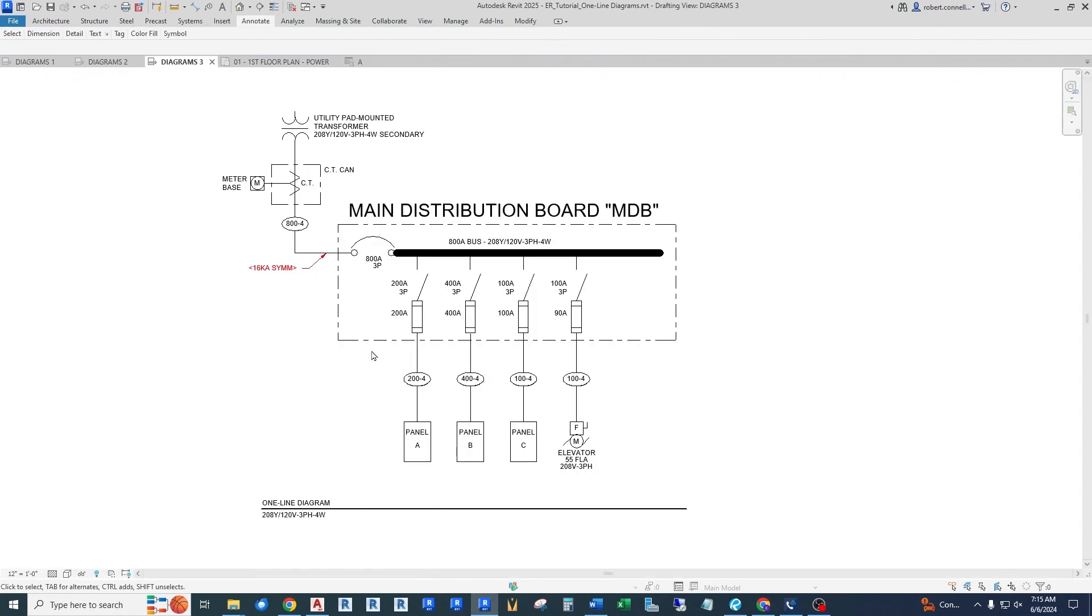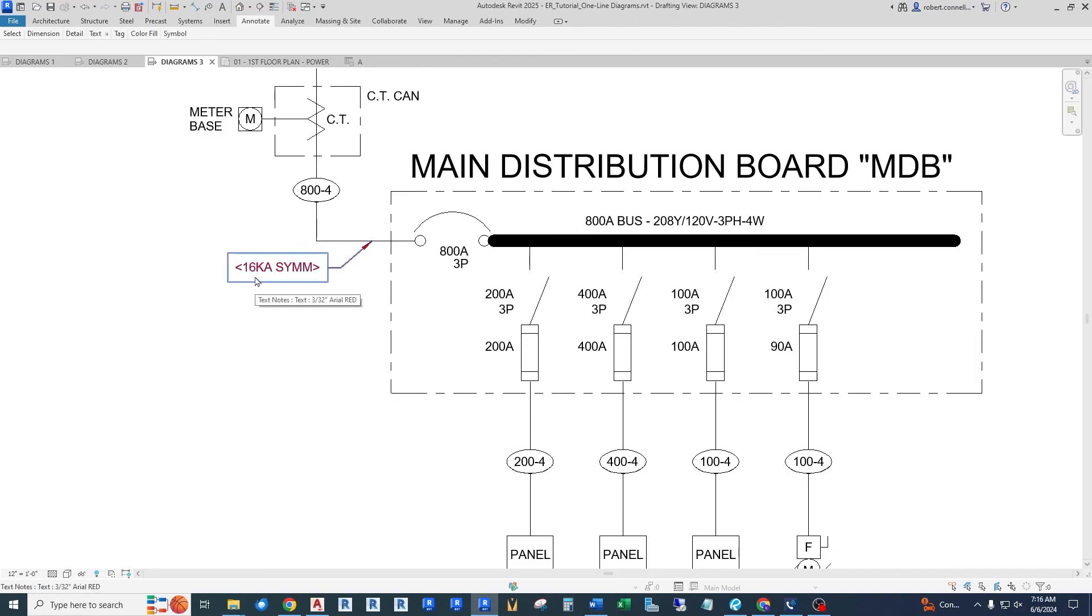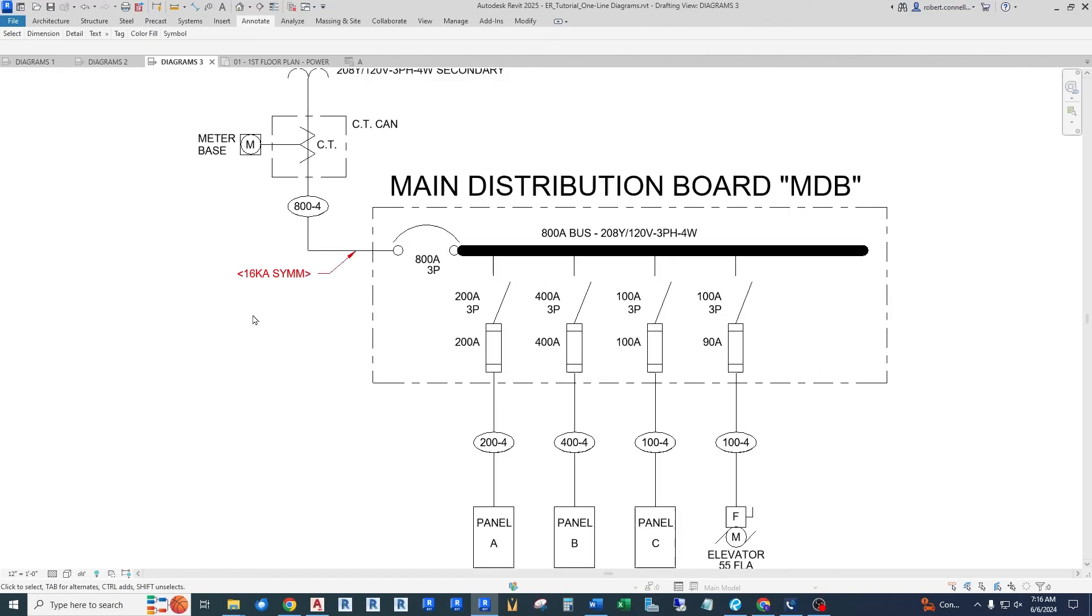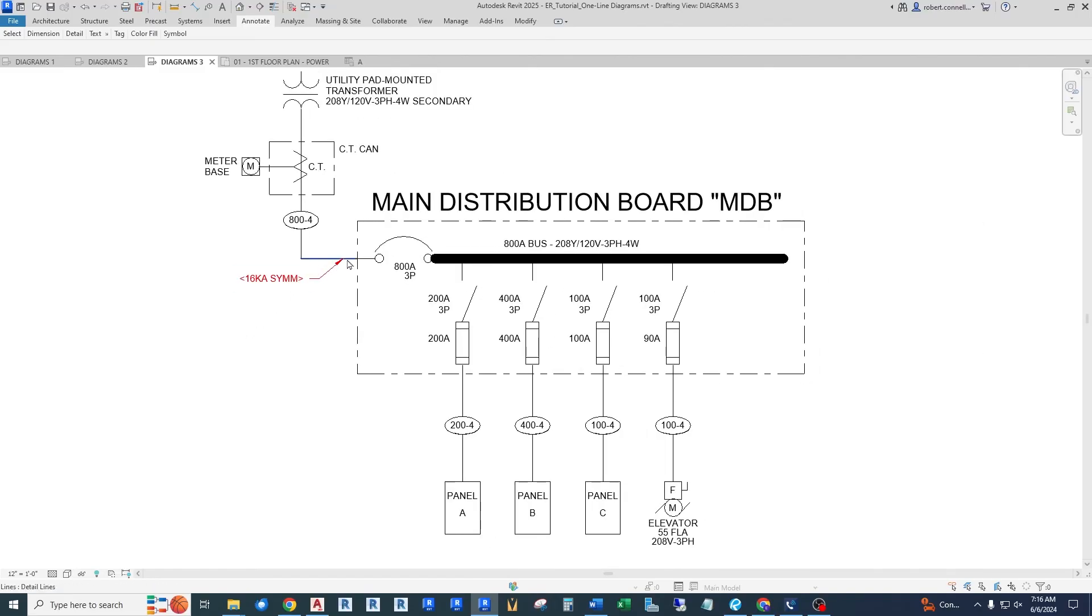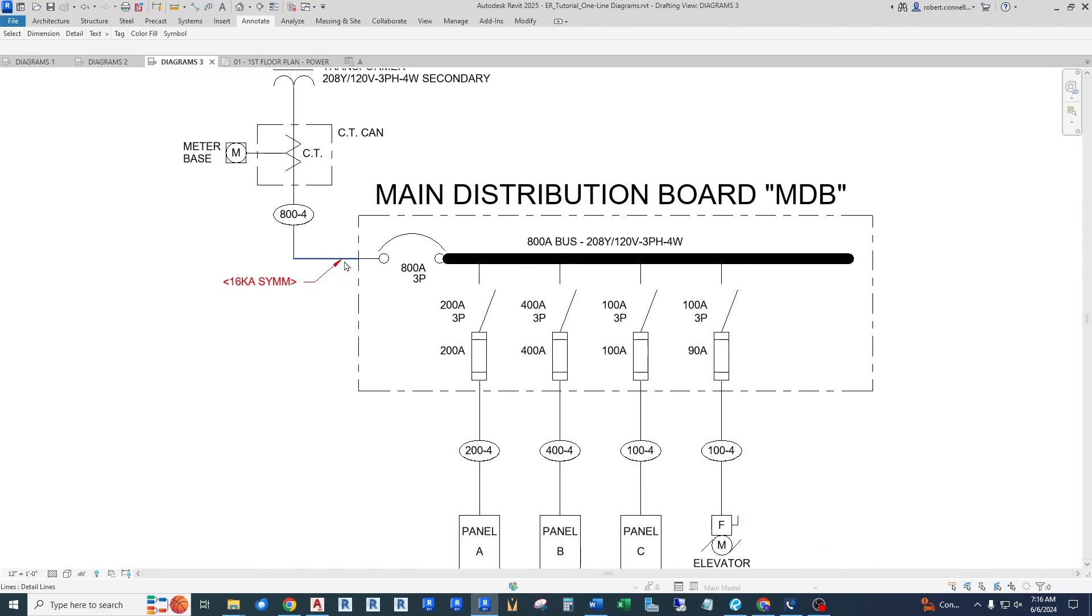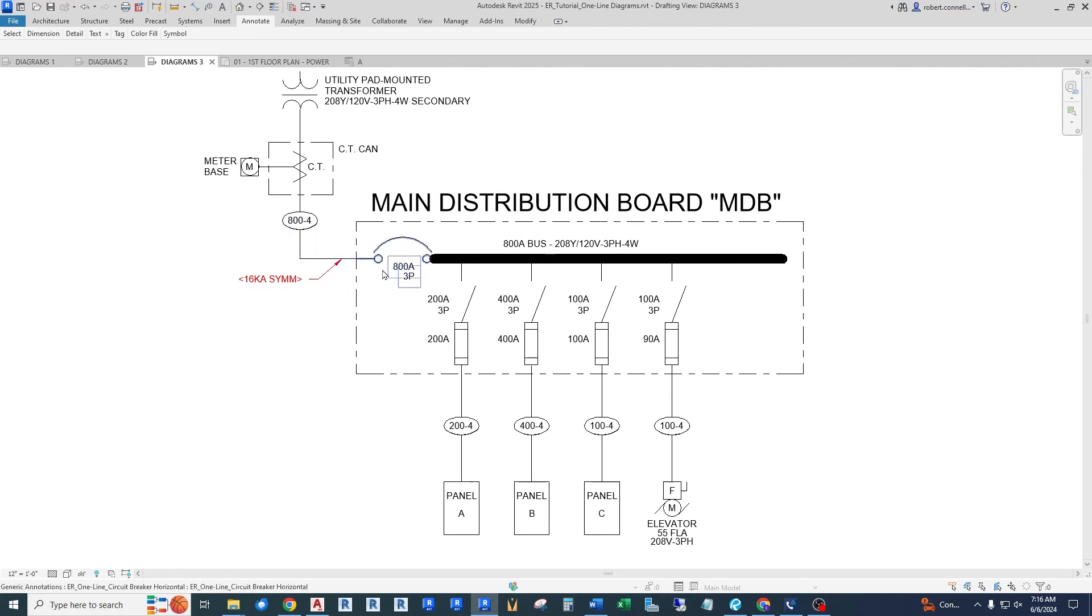Now what else can we put on this diagram besides just sizing and things like that? This here, and I've done it in red, is called the available fault current. It is the short circuit amps. This is 16 ka or 16,000 amps. Sym just means symmetrical. It's a technical term for what the waveform looks like. But the idea is, if you take these wires and connect them all together to make a short circuit, you will be drawing up to 16,000 amps instead of the 800 amps that it's rated for. This is another thing that we put onto these one line diagrams so that equipment and switches can be rated for that short circuit available.